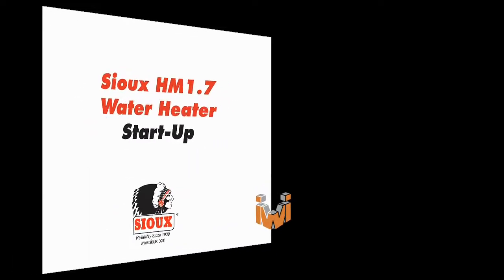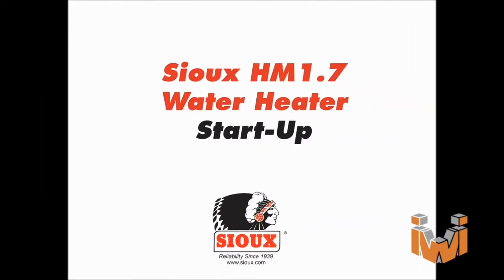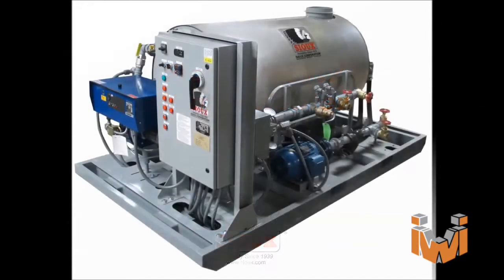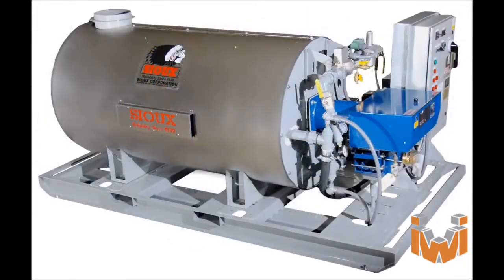The HM 1.7 water heater by Sioux Corporation is a new design building off the success of Sioux's M1, which has been a popular water heater in the concrete industry for over 40 years. The HM 1.7 is designed to provide increased flow and heat output, and a layout that facilitates ease of maintenance on key components. The improved control system makes operation simple, and the ASME-coded heat exchanger provides high-efficiency heat transfer.